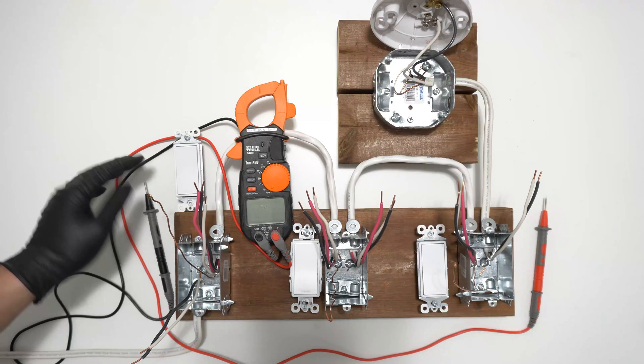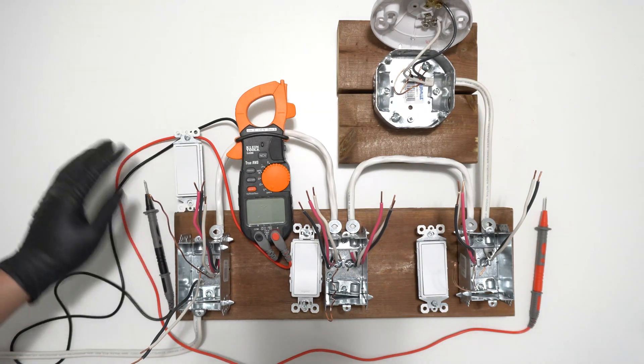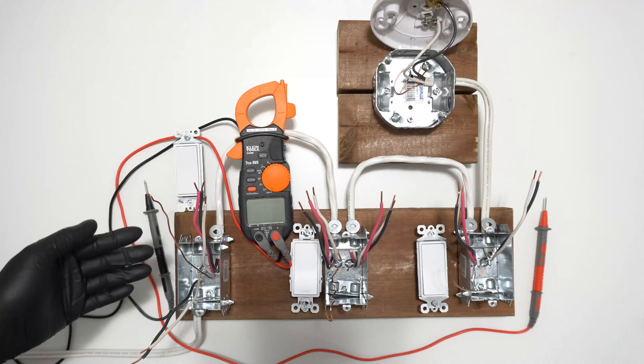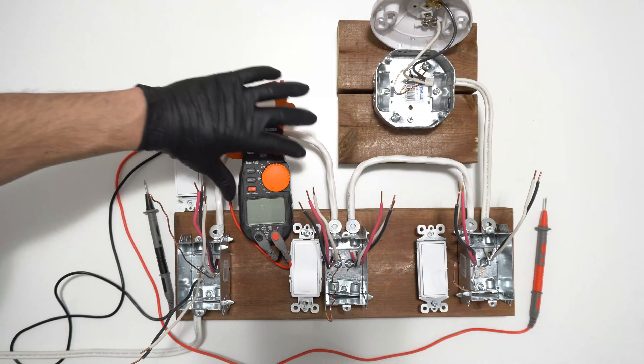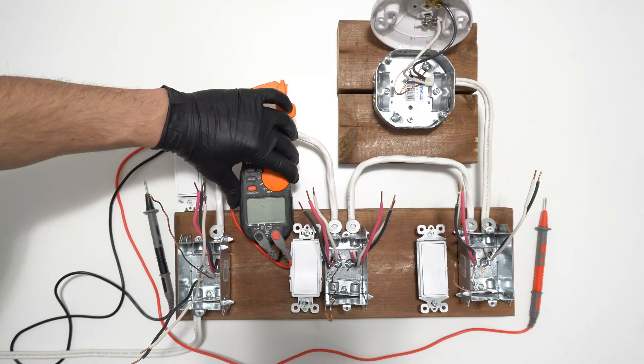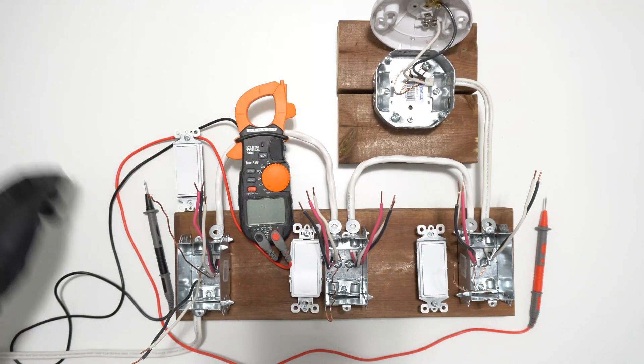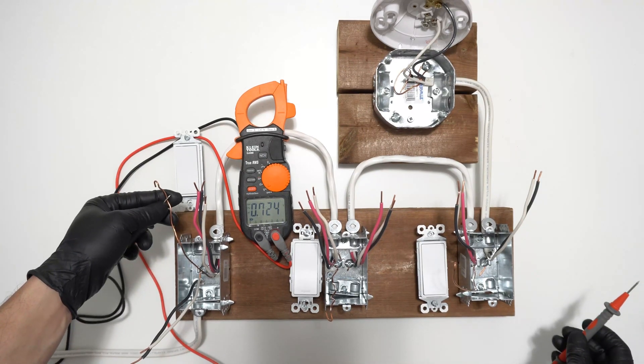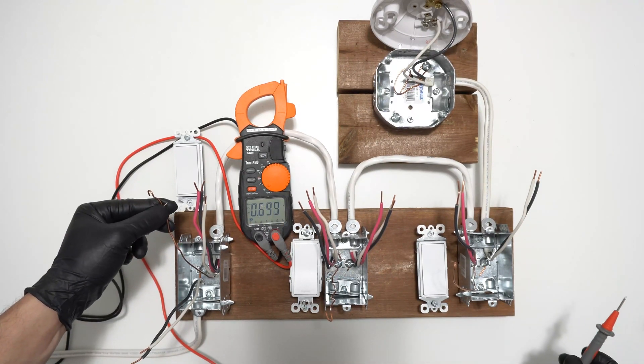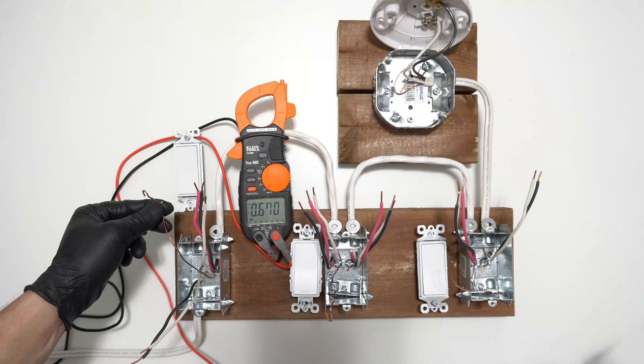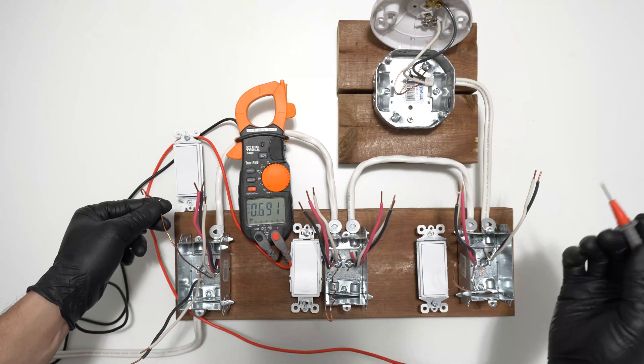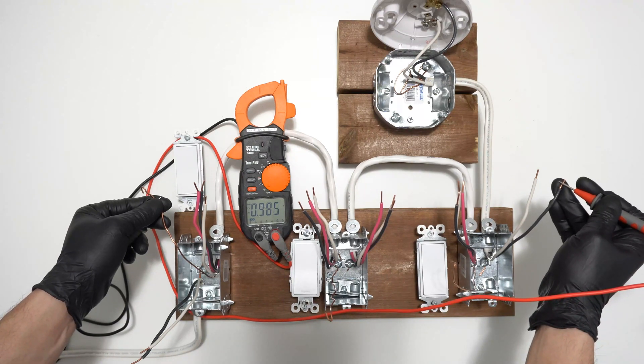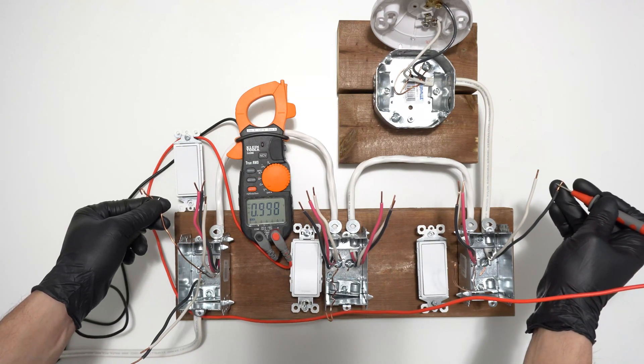If you are still unsure if you have turned off the right breaker or not, it's best to use a voltmeter to find the potential difference of the circuit. First thing we need to do is select voltage on the meter and next have one lead touching the ground wire, and hopefully all the ground wires are bonded and connected properly. Next we will have the other lead touch all the wires to see if there's a potential difference close to 120.